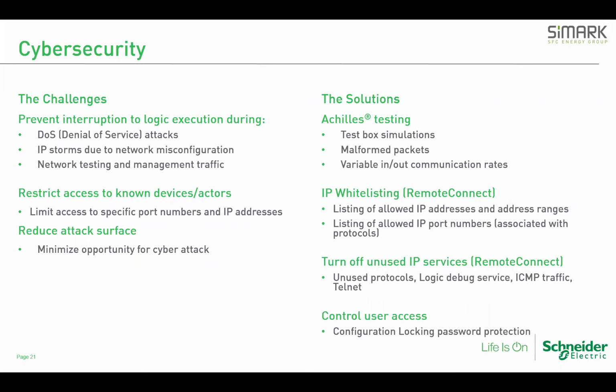A lot of work has been done improving the cybersecurity and resiliency of these RTUs to things like malformed packets coming in over the Ethernet port. So if there's a denial of service attack occurring, a lot of Ethernet traffic, the port is capable of filtering this out and not sending it on to the application code and potentially causing a slowdown in the RTU's execution or any problems with execution of the program due to a storm of Ethernet traffic. And that's a good way of making sure that the control continues to happen under numerous different conditions.